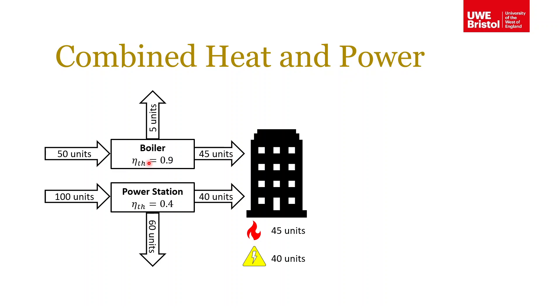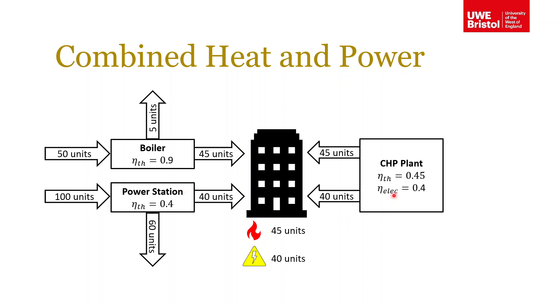That's how we would conventionally supply power and heat to this building — through the power station and through a boiler. Now let's replace this with a combined heat and power plant. This CHP plant provides our 45 units of thermal energy and our 40 units of electrical energy. Let's say the electrical efficiency is the same — that's a reasonable assumption since it operates on similar thermodynamic cycle principles. Let's say the thermal conversion efficiency is lower, around 45 percent.